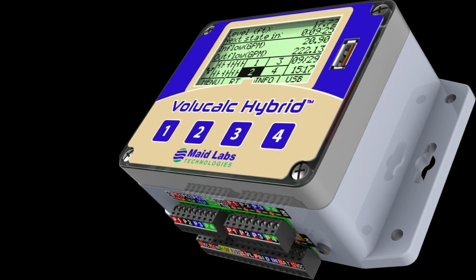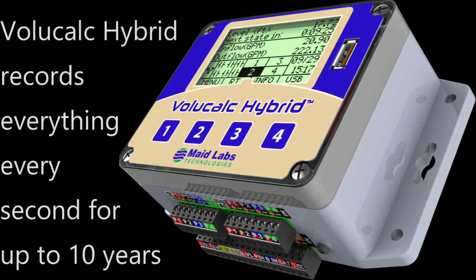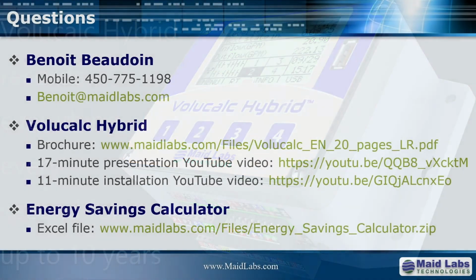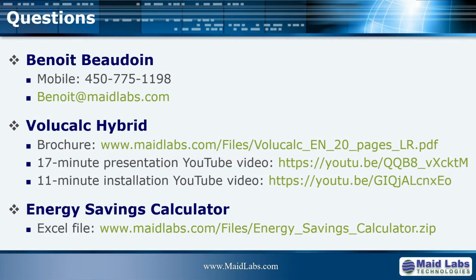If you have a good SCADA system, make sure that it's working properly by cross-checking what you're getting using a device like this one. If you don't have any SCADA system, this can be just the heart of it. It doesn't replace a controller or anything like this, but it monitors perfectly what's going on inside the lift station.